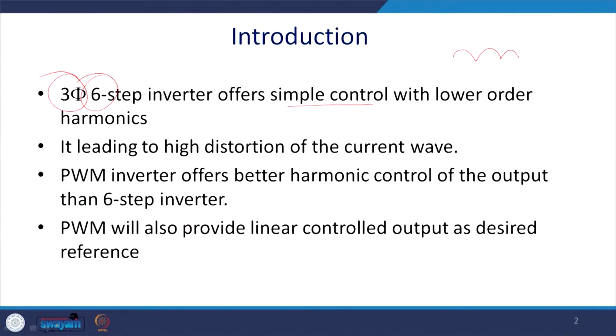It is essentially the 6 step. You will find harmonics of the order 6n plus minus 1, and the output voltage will have a ripple of 6 steps in a cycle, because one pair of diodes conducts for a 120 degree mode. That is common to all adjustable speed drives, because there is a front end which may be a passive rectifier.